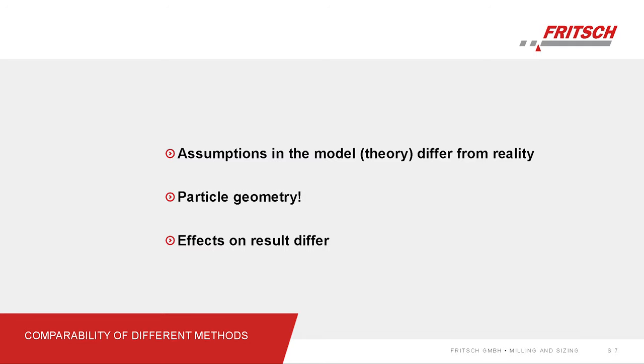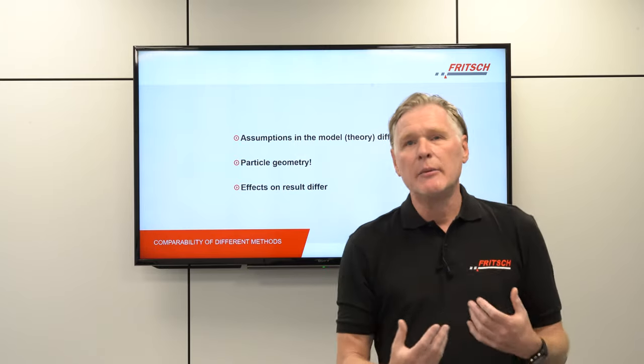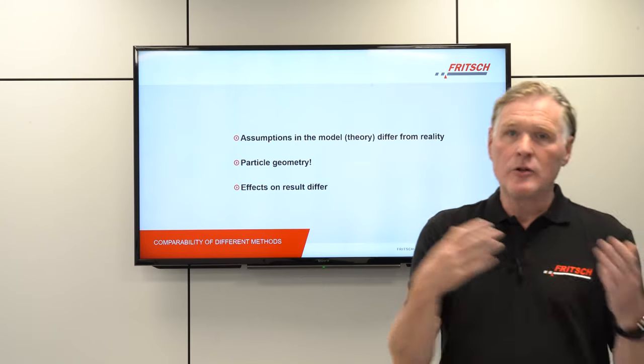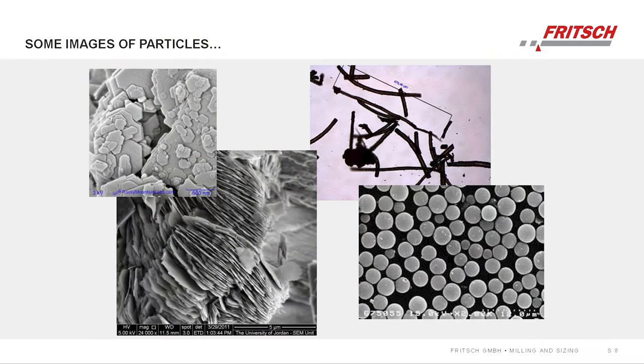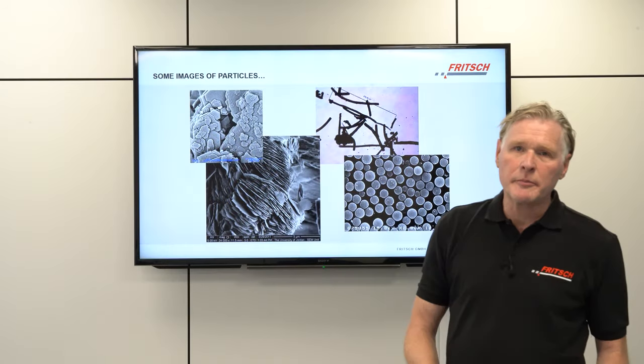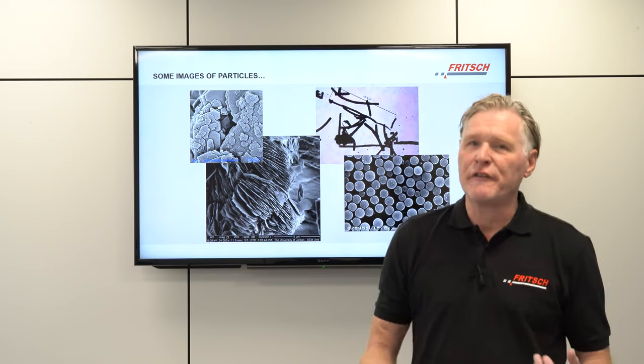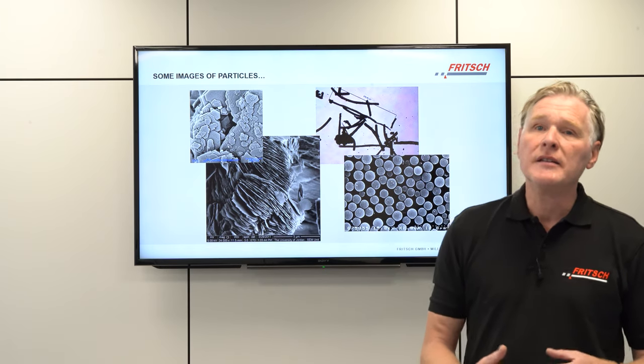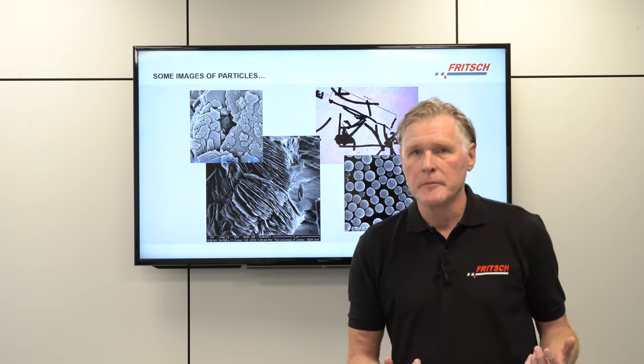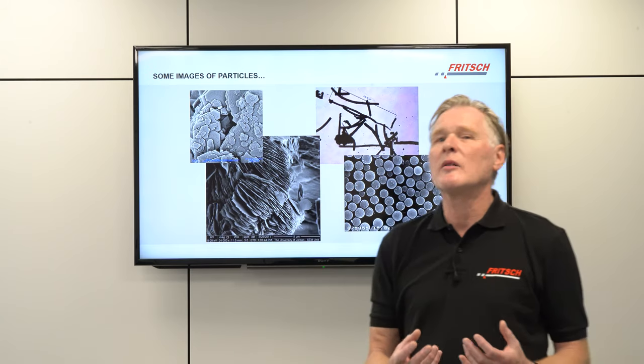Unfortunately the effect of different particle shapes on the result is not always the same, so from one technique to another you will see some variation in results. Here on the left hand side you see electron microscopy images of clay. Clay is very often measured using sedimentation, and sedimentation based on Stokes equation assumes particles are spherical. As you can see, clay is very flaky and far from spherical, so in principle the result will be wrong.